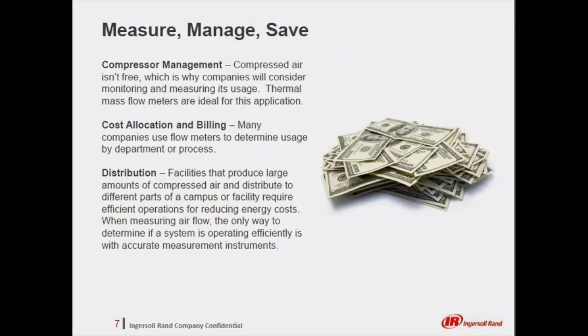With compressed air being the most expensive utility, measuring, monitoring, and acting on the results provided by the flow meters is exactly why companies will consider their installation. Many companies use flow meters to determine usage by the department or even a process, and distribution of air among different parts of a campus or a facility relies on efficient operations to successfully reduce the energy costs. And this can only be accomplished with accurate measurement instruments.